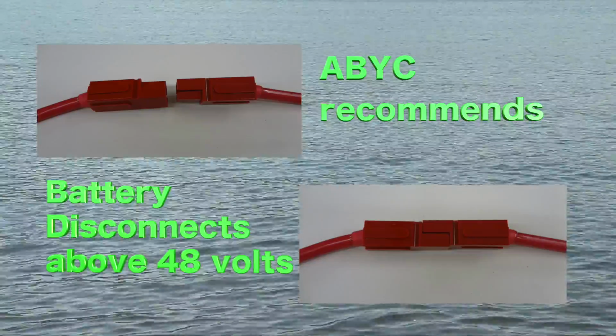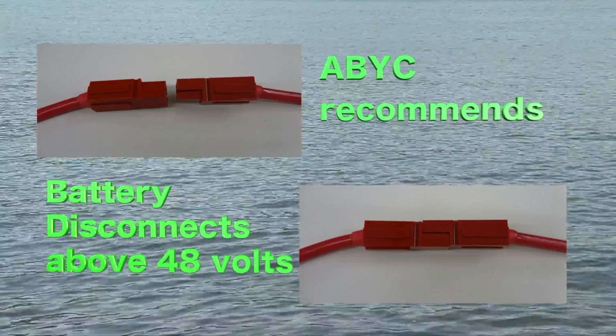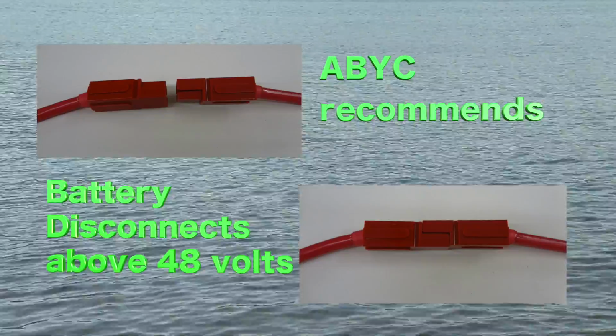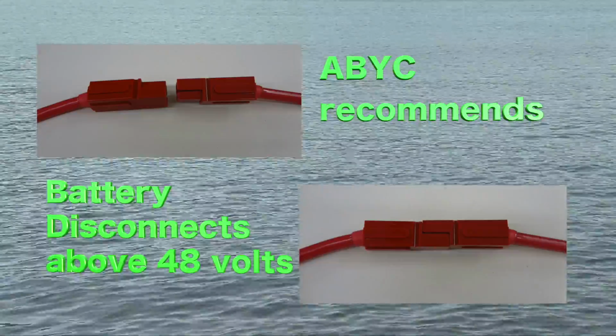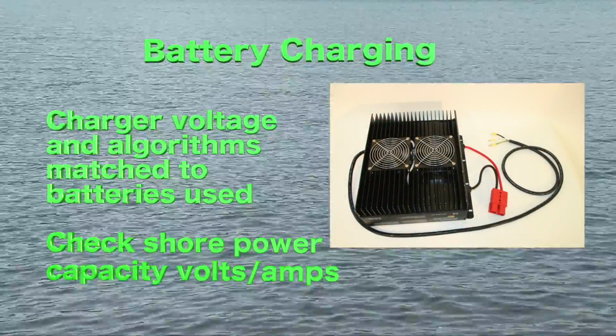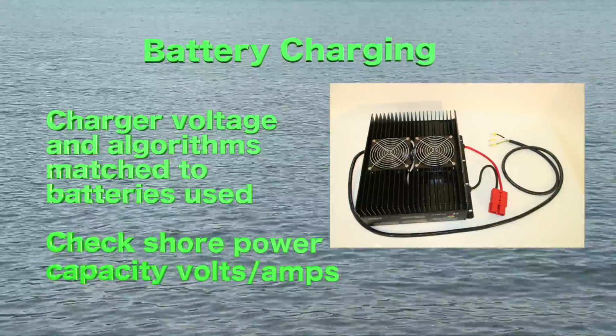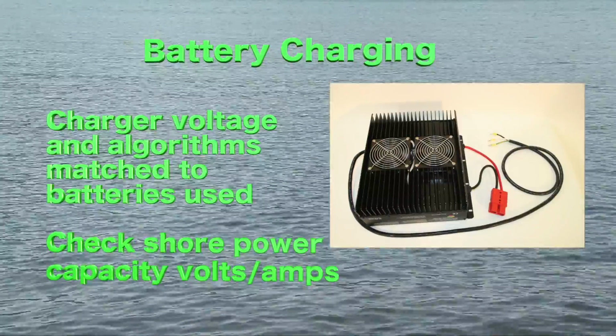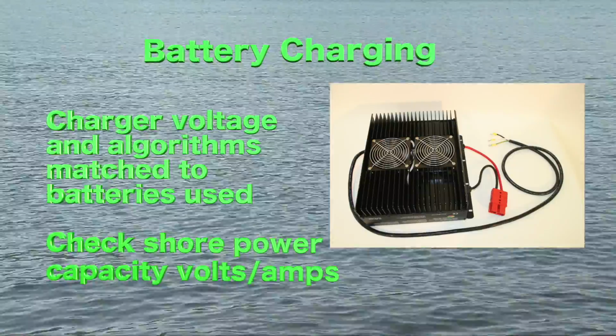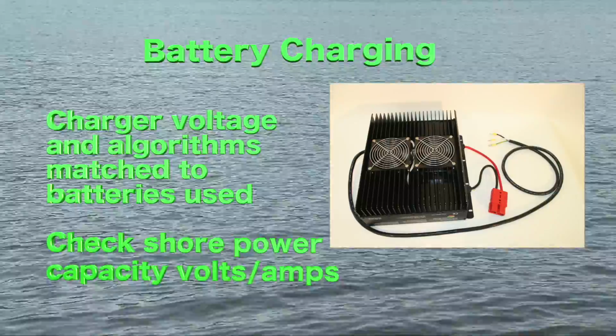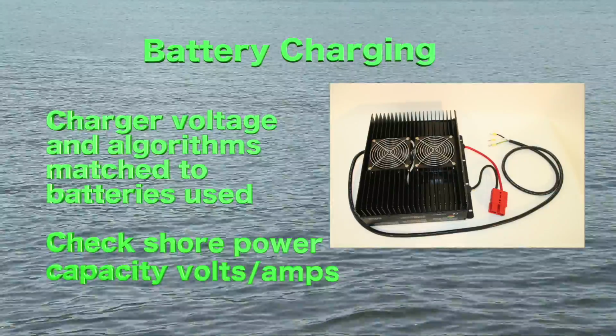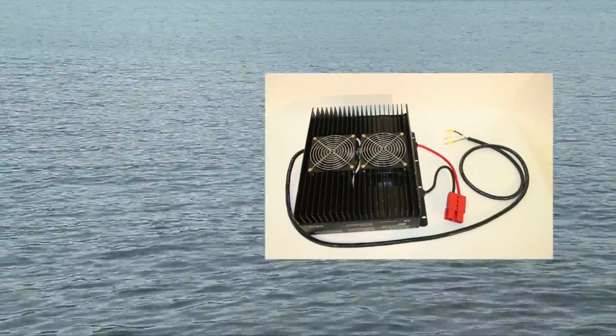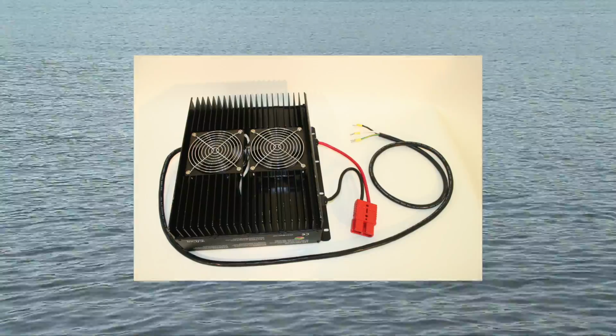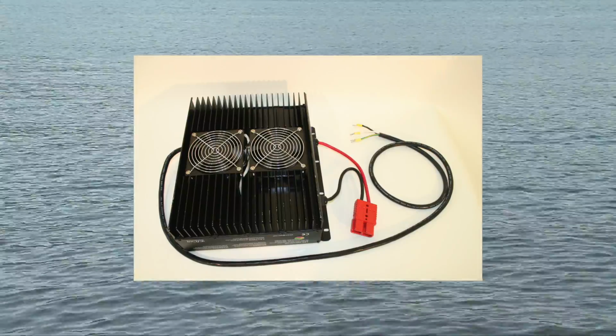If your system of batteries exceeds 48 volts, or you are connecting additional battery strings of 48 volts and higher, ABYC guidelines call for disconnect plugs at no more than 48 volt intervals so that the system may be safely serviced by disconnecting batteries. You will need to install one or more battery chargers depending on your battery array and battery manufacturer recommendations. Charging algorithms of the charger must conform to the battery charging requirements. Available shore power and the rate of charge desired will be factors in selecting the size of the battery charger. Battery chargers provided by Elco are factory set to properly charge many AGM batteries using established algorithms.